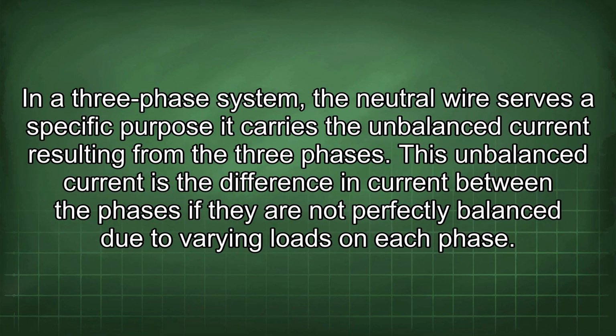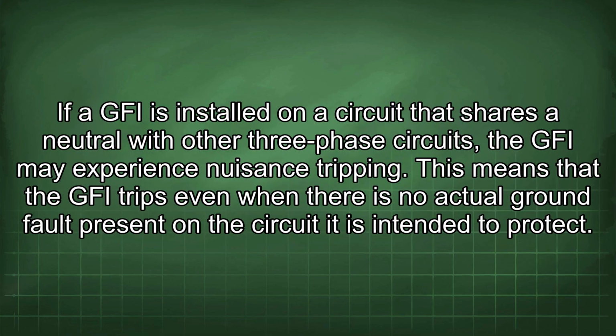In a three-phase system, the neutral wire serves a specific purpose. It carries the unbalanced current resulting from the three phases. This imbalanced current is the difference in current between the phases if they are not perfectly balanced due to varying loads on each phase. If a GFI is installed on a circuit that shares a neutral with other three-phase circuits, the GFI may experience nuisance tripping.